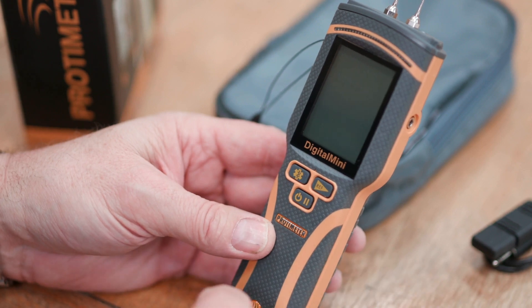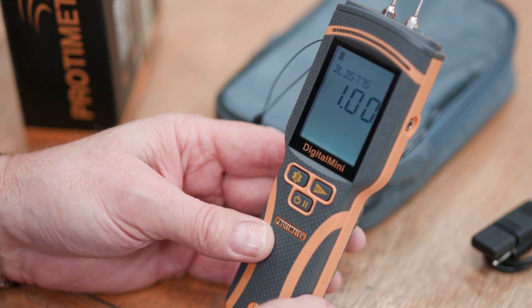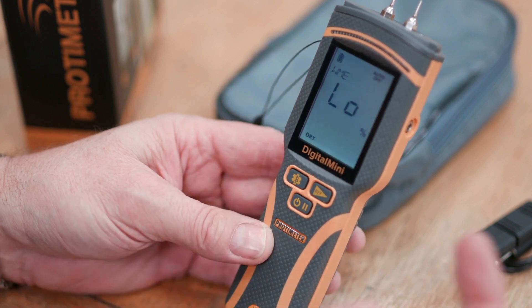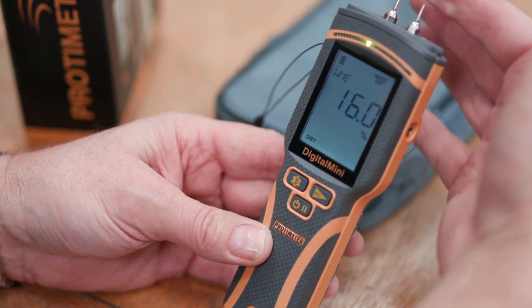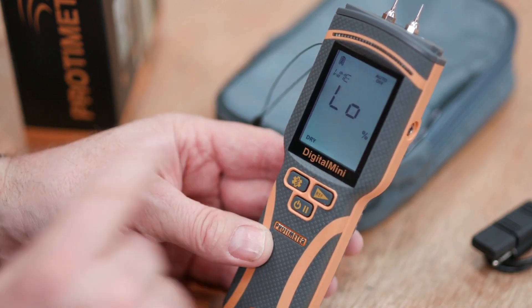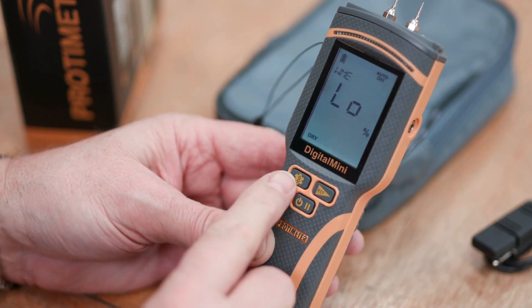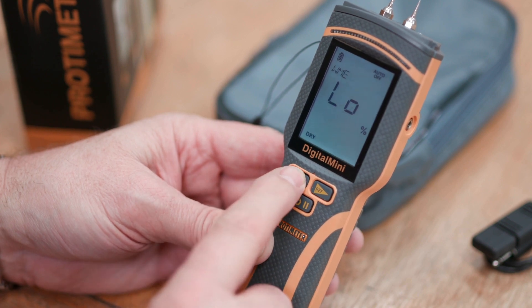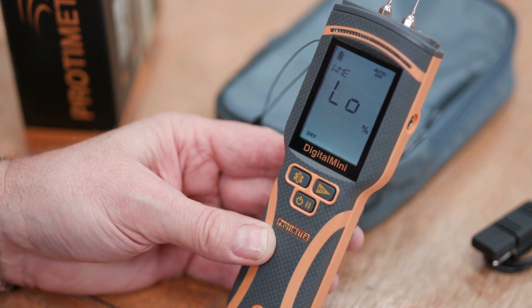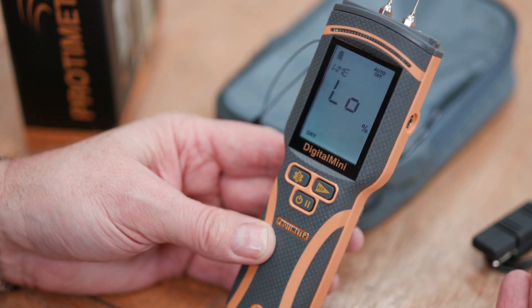Now let's take a deeper look at the functions. To turn it on, press and hold the lower button. On the display you'll see a low symbol, meaning it's below range — that disappears as soon as you get a reading. On the top left you'll see the battery indicator, and at the bottom it shows dry, at risk, and wet. To turn on Bluetooth, press and hold the Bluetooth button; you'll see the Bluetooth symbol appear, flashing because it's not yet connected to the Protimeter Connect app.